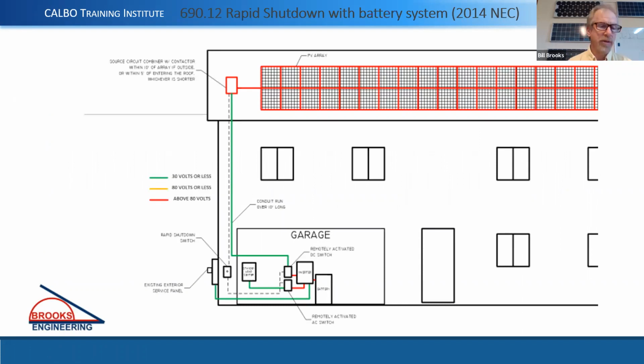Rapid shutdown for battery systems. Without going into any detail here, in the 2014 NEC, which was the 2016 California Electrical Code, there was a basic requirement to shut down the whole PV system, which would include batteries, outputs, and stuff like that. The current version of the code that we're on, which is the 2019 California Electrical Code, only requires the PV system to be shut down. And we spent a lot of time in the 2017 code defining what a PV system was.